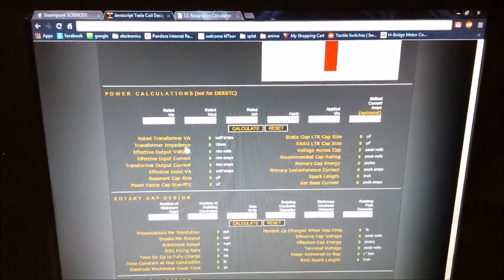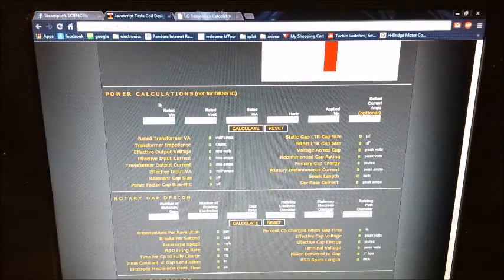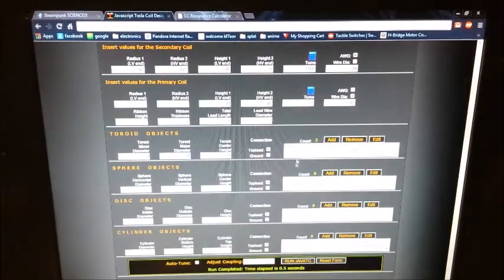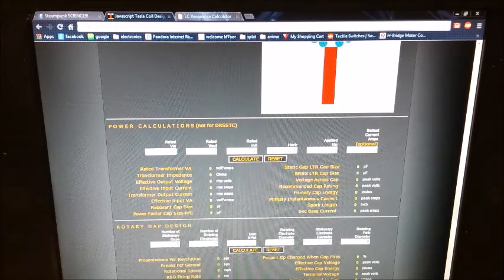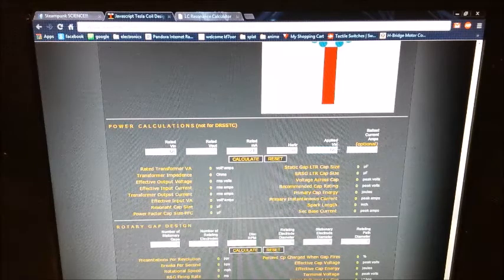I'm going to scroll down here to my rated voltage in for my power supply. Now, I have to stress that you have to enter this in before you can do anything below it. This takes everything else into account. My input is 120 volts. My output of my power supply is 7500 volts, 240 milliamps, 60 hertz because I'm in the United States of America and that's what it is. If you are in the United States, it is 60 hertz, most likely. In any other country it's also going to be that, or 50, but 60 is a good value. I put 120 as my applied voltage in, because that is exactly what I'm doing. Calculate this.